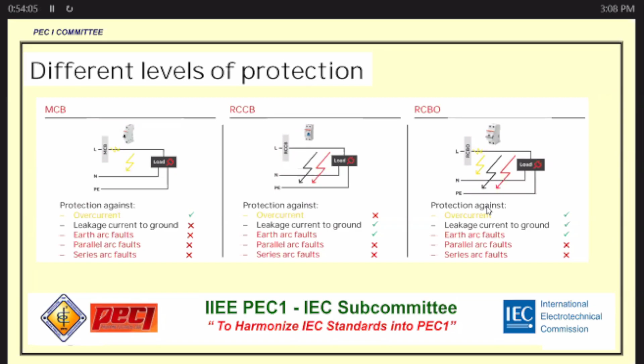Now how about the arc fault detection device with integrated miniature circuit breaker? This gives us protection but excludes leakage current to ground, or what we call residual current. Then the most complete one is the arc fault detection device with integration of residual current breaker and overcurrent protection.